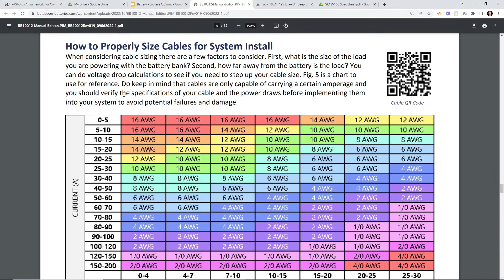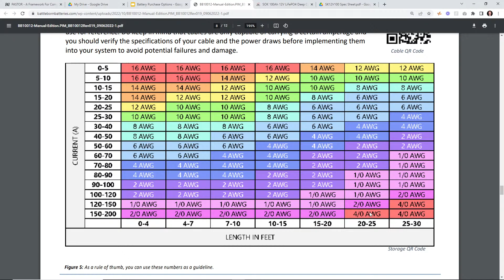And then they actually give you a little chart on how to size the cables properly. So these are the cables that are connecting each battery to themselves. If you have a 100 amp hour battery connected to a 100 amp hour battery, you have the potential of 200 amps to be pulled through that battery. So if you look at this chart, you've got 150 to 200 amps being pulled through, you're looking at a 2/0 gauge wire, and that's what we used on Thomas's van. You can see the longer you go, the bigger the wire you need. Actually, I think we used 4/0.